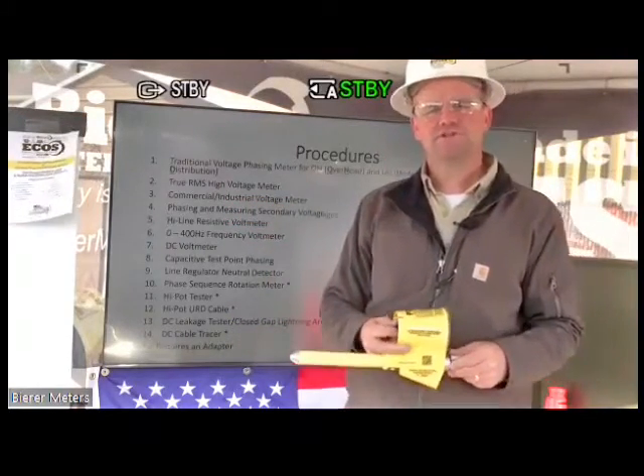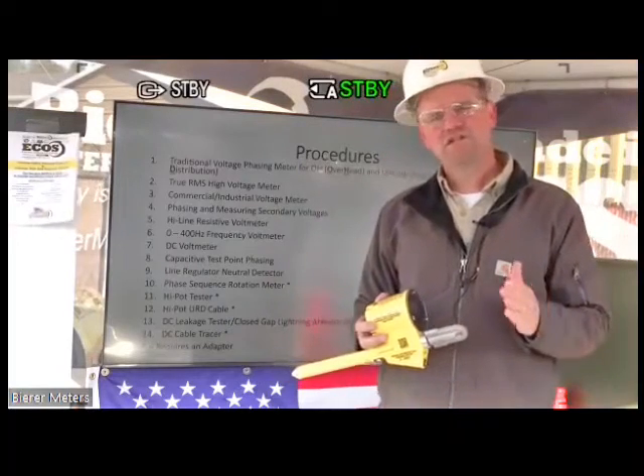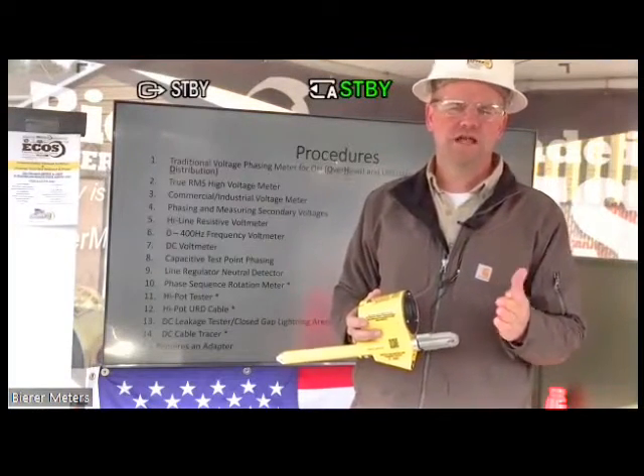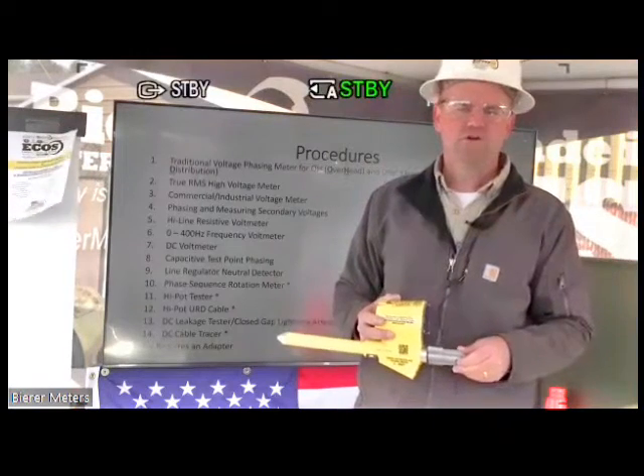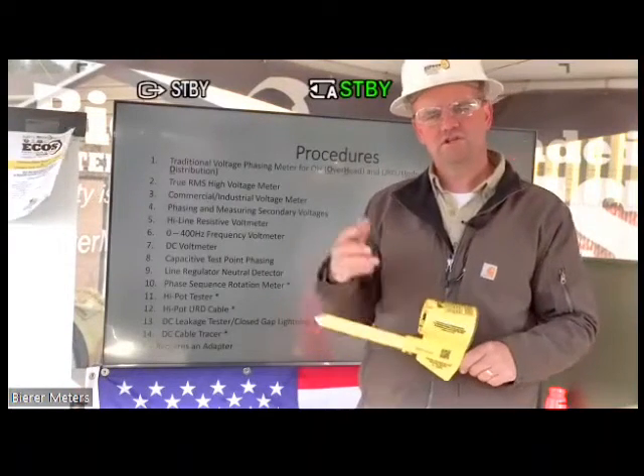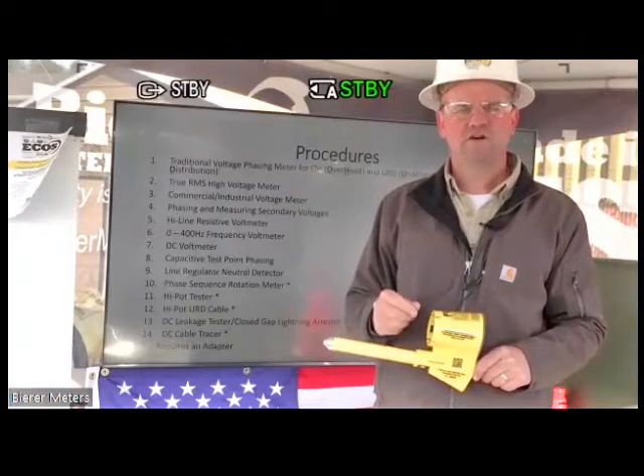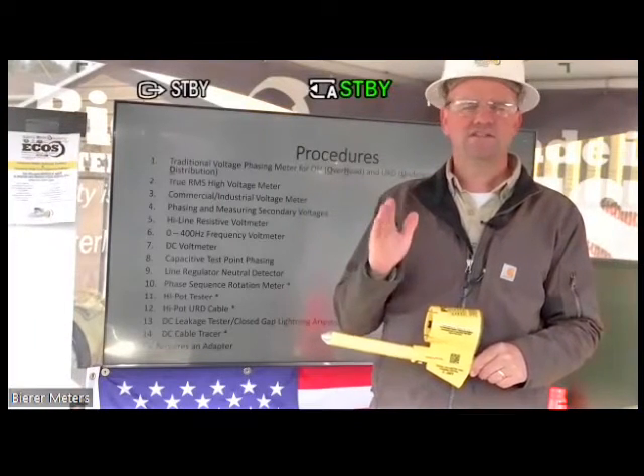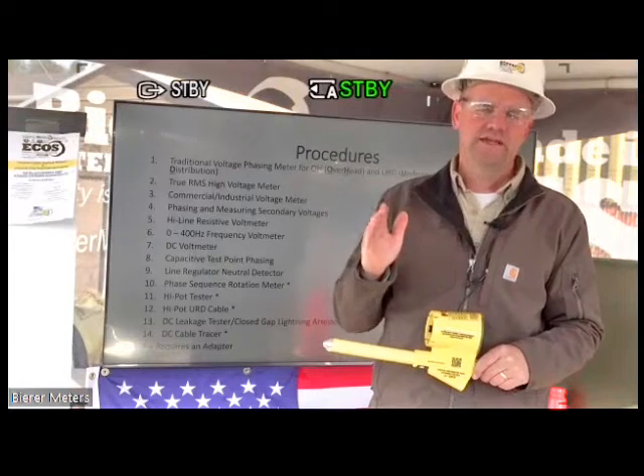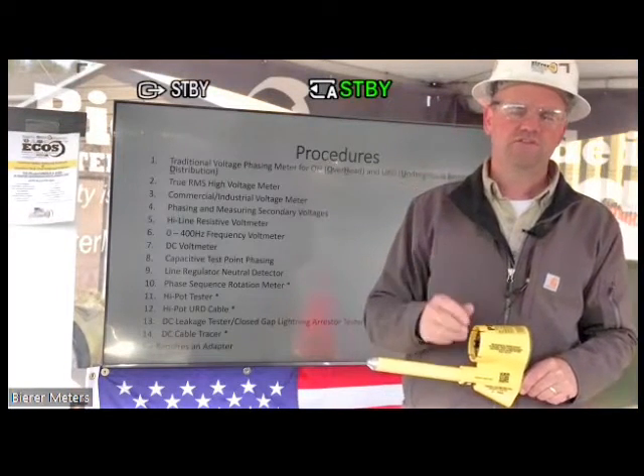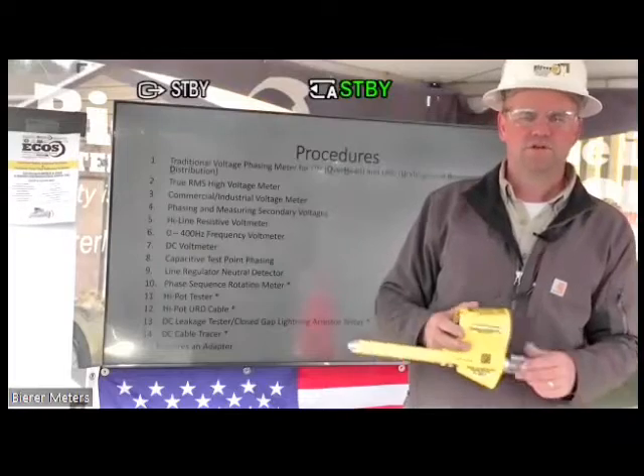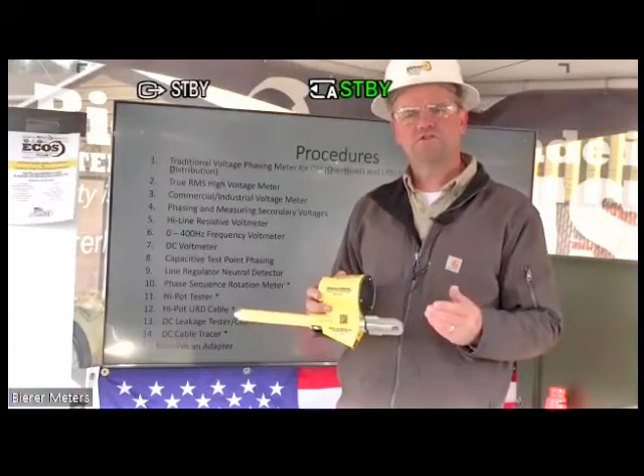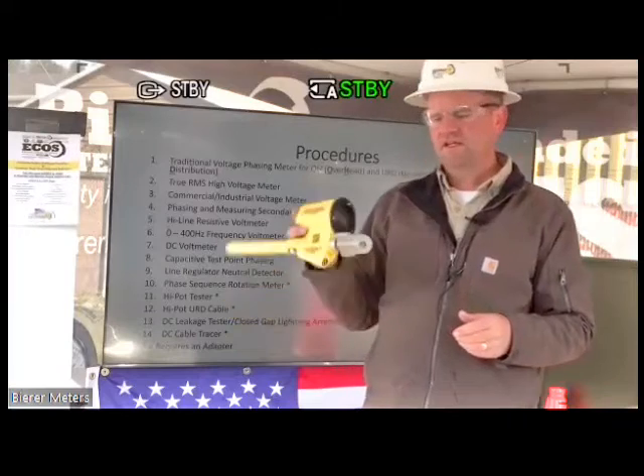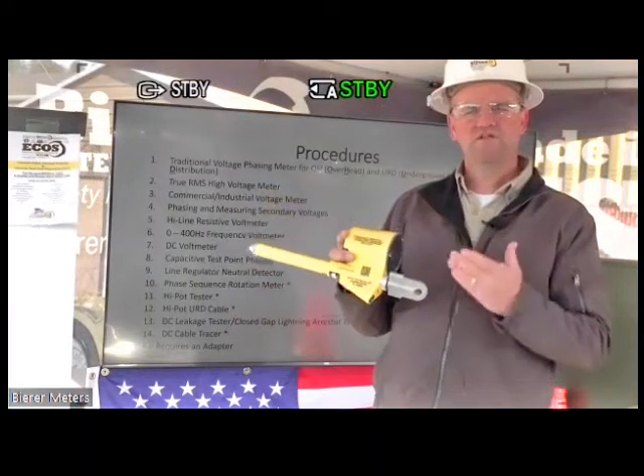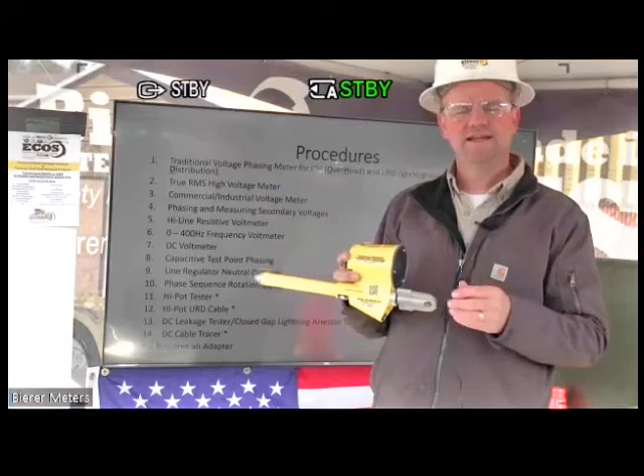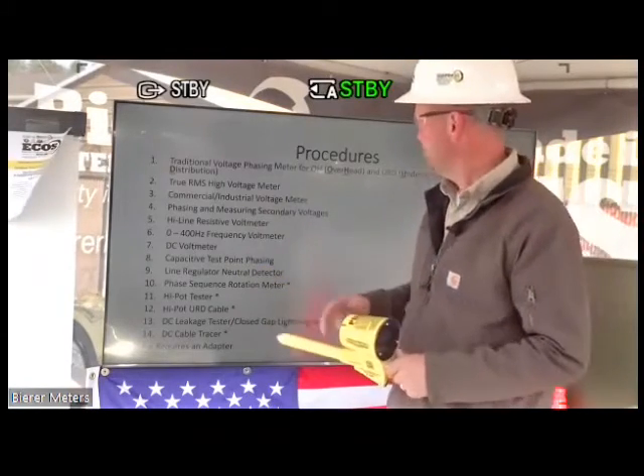So a lot of C&I customers that you may have, voltages that are in a little bit of a gray area. So as an example, 4160, that voltage is actually hard for a traditional phasing meter to display, because usually on the lower end of the scale, it becomes very inaccurate and it tends to want to show zero even if the voltage is not zero. So all those C&I customers, the lower voltages, the 2 kV, the 4160, this tool works remarkably well because you can distinguish those potentials really easily and extremely accurately.